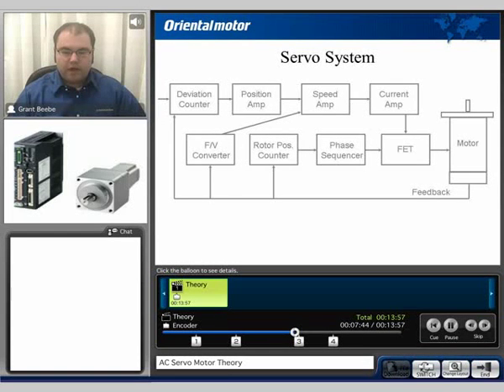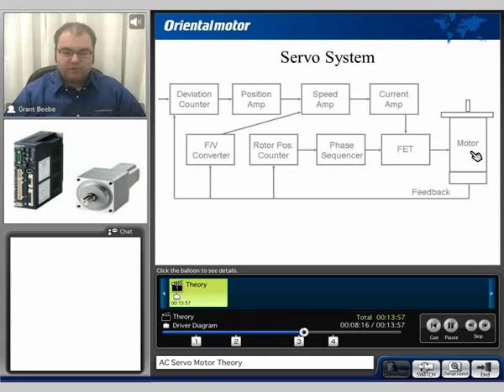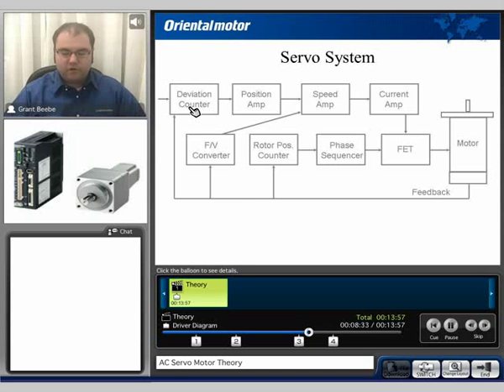What makes a servomotor a servomotor is primarily the feedback sent back from the encoder. A servomotor is actually based upon error. Information comes in through this block diagram into the deviation counter. That information is then sent to a position amp, a speed amp, and then a current amp, and then we activate the FET transistors in order to generate motion and run at a specific speed and hopefully a specific distance. Because of the design of the motor, information is then sent back through the encoder and put into the deviation counter, which compares the actual commanded position to where the actual position of the motor is.